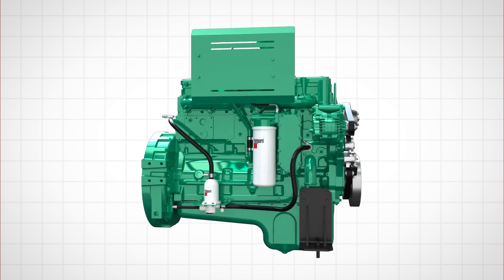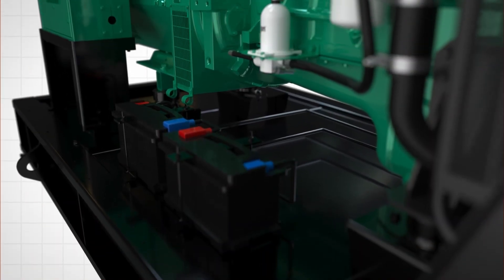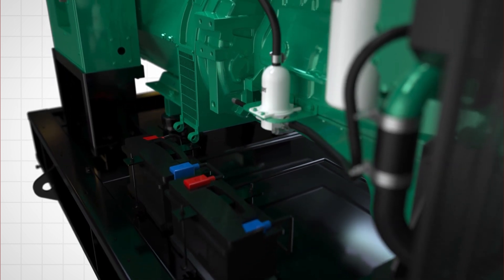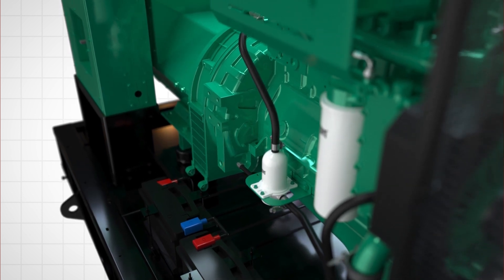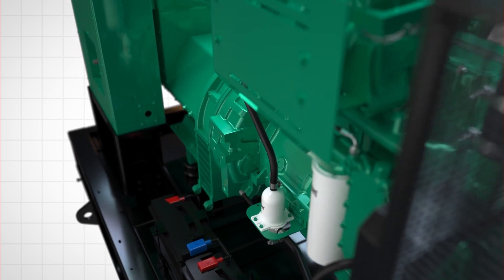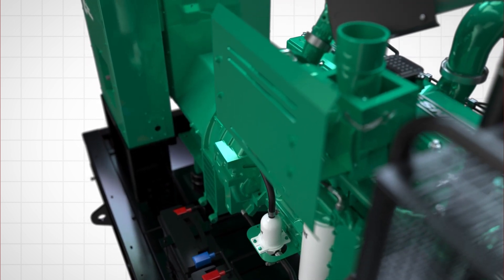Can you elaborate a little more about the features of the PSO60X controllers? The PSO60X series controllers are robust, with features similar to the PC 1.2. It provides automatic start/stops, transfer and retransfer of load. Metering features include alternator and genset power and energy parameters — voltage, frequency, current, power factor, kilowatt, kVA, kVAR.